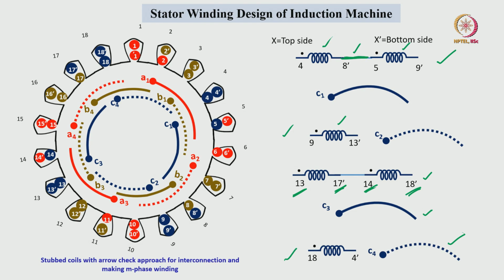We can see here in a fractional slot winding, the number of stubbed coils is coming 9, but with respect to the 3/2 slots per pole per phase, or 3/2 number of coils per one stubbed winding, which is not possible. Because of that reason, one stubbed winding we have done with 2 coils, other stub winding we have realized with 1 coil. So that cumulatively both stub coils have 3 windings. Okay.